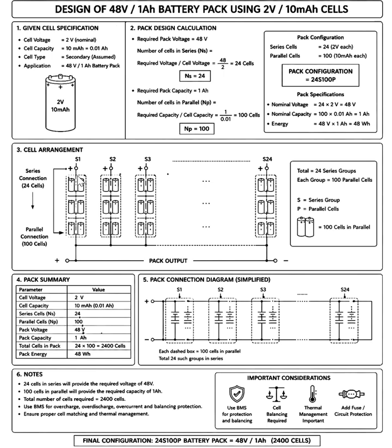So group 1 is capable of carrying 1 ampere hour. Similarly, if you consider all these groups, each group will be capable of carrying 1 ampere hour. As all these groups are connected in series, a series circuit should carry the same current, right? That's why we design each group to carry 1 ampere hour.